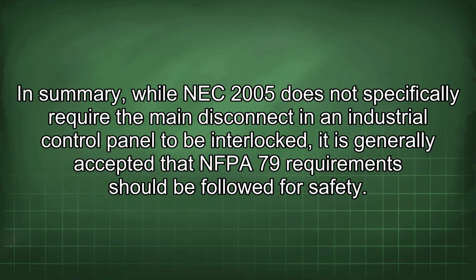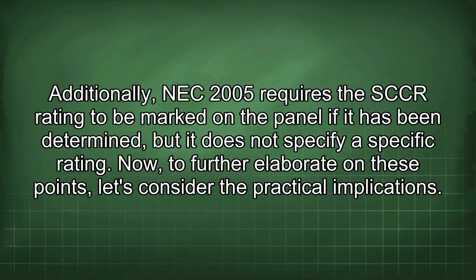In summary, while NEC 2005 does not specifically require the main disconnect in an industrial control panel to be interlocked, it is generally accepted that NFPA 79 requirements should be followed for safety. Additionally, NEC 2005 requires the SCCR rating to be marked on the panel if it has been determined, but it does not specify a specific rating. Now, to further elaborate on these points, let's consider the practical implications.